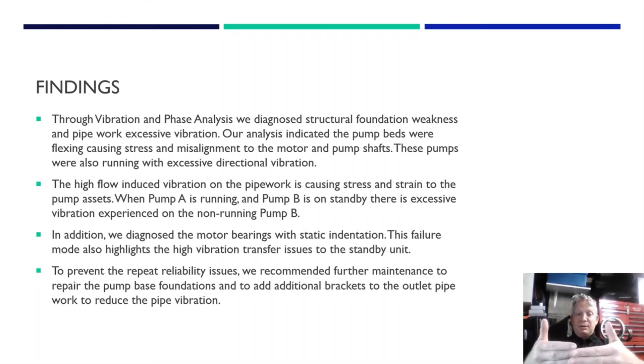So in addition, we diagnosed the motor bearing defect, static indentation. So you imagine the spare pump sat there, the stationary pump, while the other pump's running. Because of the historical issues, operators don't like changing pumps. When it's running, they want to leave it alone because things keep breaking, which is okay, but they leave the one pump running and your stationary pump stood there. So that bearing here is from the stationary pump, the spare, the backup unit. So that stood there, and you can imagine all the vibrations from moving on the bed plate, the pipe's moving and it's transferring because the outlet of the pumps come together. That gave it a static indentation.